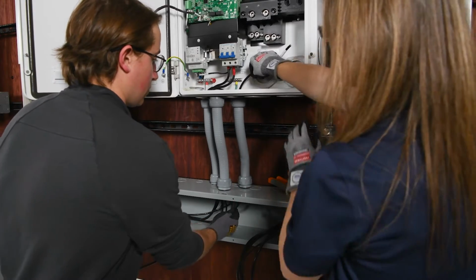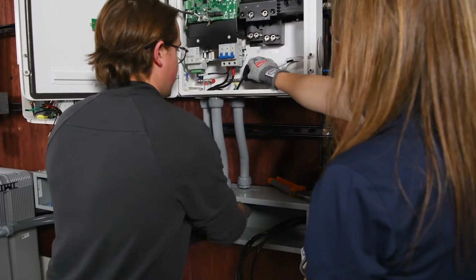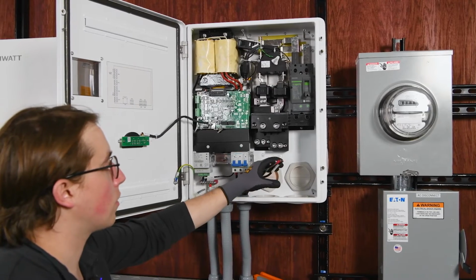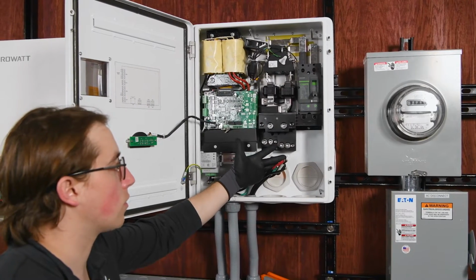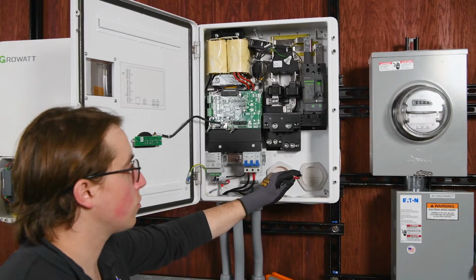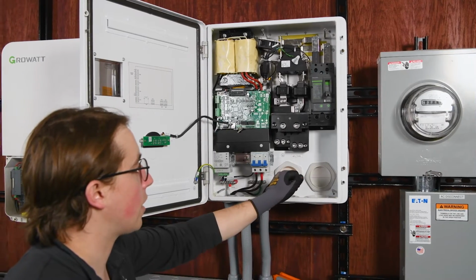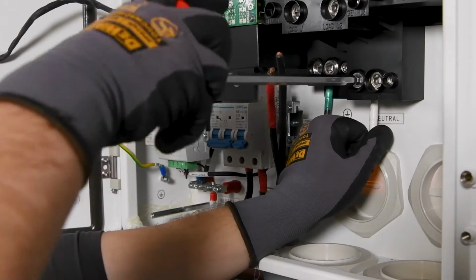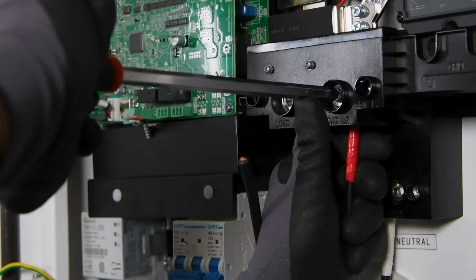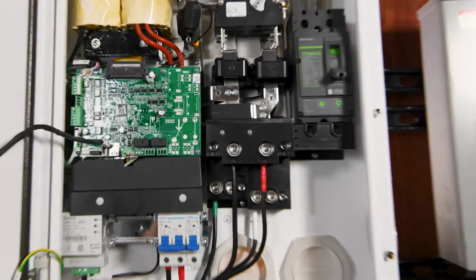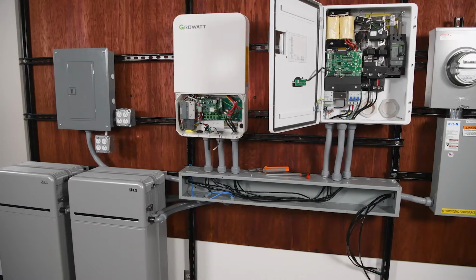We've pulled our conductors from our load panel to the SYN. Again, if you're going to have a larger backup panel, then you'll need larger conductors. But for us, we're just going to be using a 60 amp breaker, and we have our 6-gauge wire here. We'll connect our neutral, our ground, and then our 2 hot conductors from the SYN terminals here to our load panel.